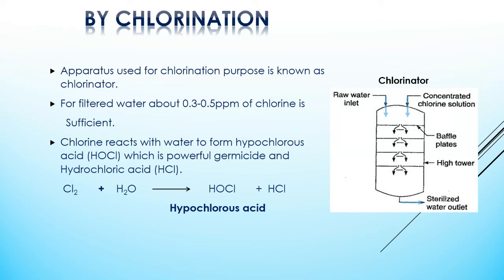For filtered water, about 0.3 to 0.5 ppm of chlorine is sufficient. Chlorine on hydrolysis produces hypochlorous acid, which is a powerful germicide. This hypochlorous acid reacts and inactivates enzymes in the cells of microorganisms, which leads to the death of harmful bacteria. Chlorination is an effective and economical method which can be used at low as well as high temperatures, and introduces no salt impurities in water.